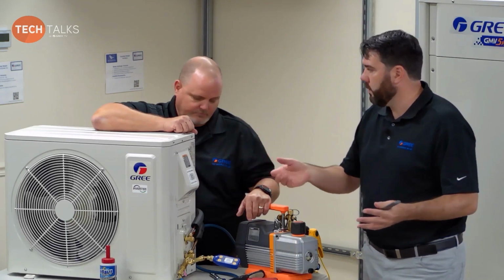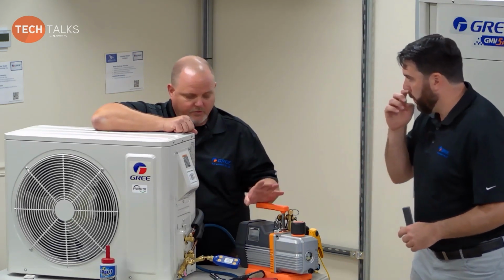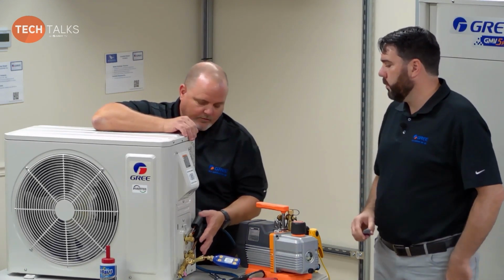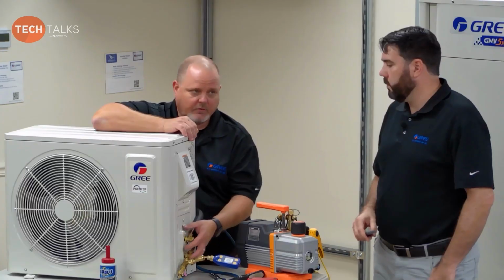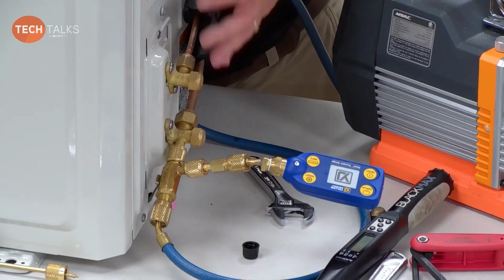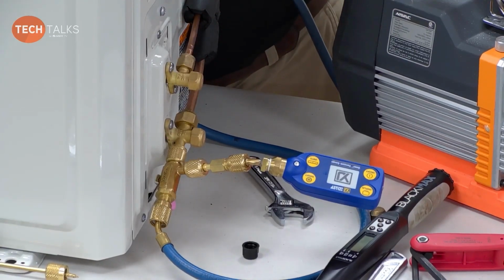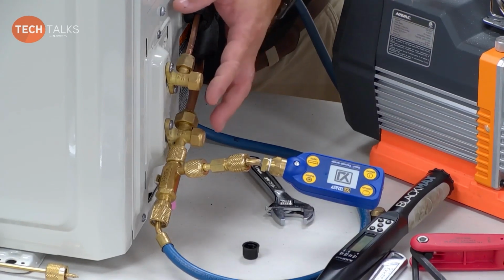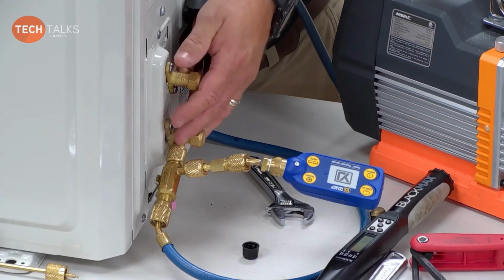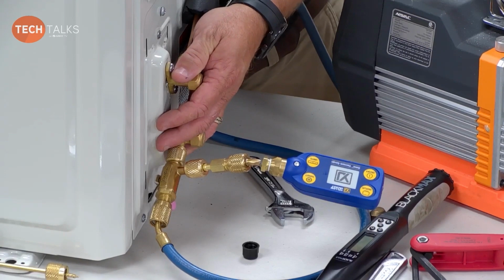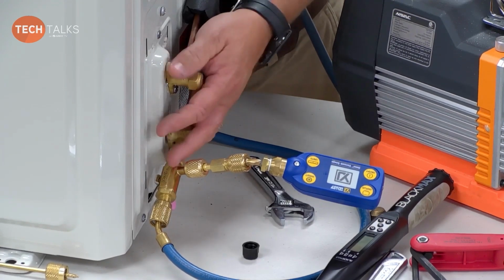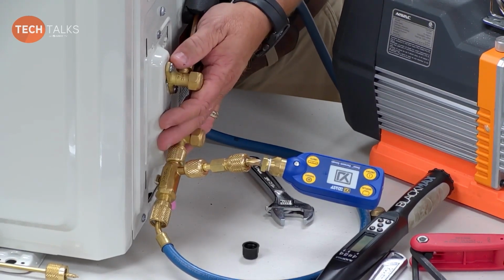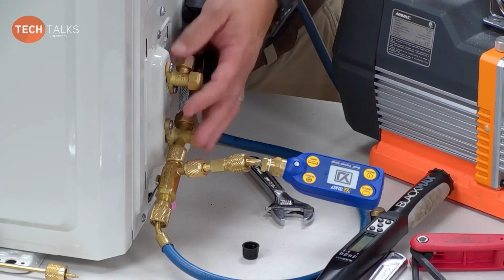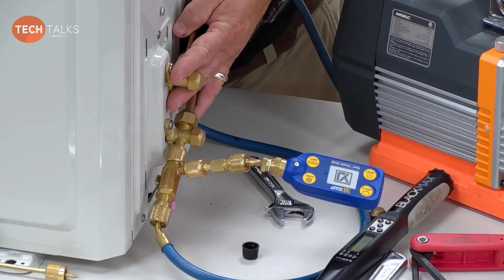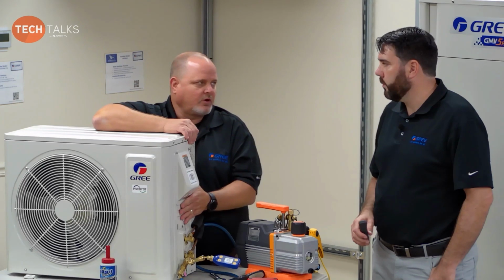Now, once you've done that and you open A and B and C and D, then the refrigerant is shared throughout the entire system. So one caveat to that, and this is my opinion, it takes longer if you've got a multi-zone unit to pull down each circuit separately. But what you've got to keep in mind is if you pull down one of those circuits and one's not holding, you've just saved yourself time. Because now a circuit must have a leak. So while I'm trying to figure out where I'm leaking on A circuit, I've got my vacuum pump running on my B circuit.